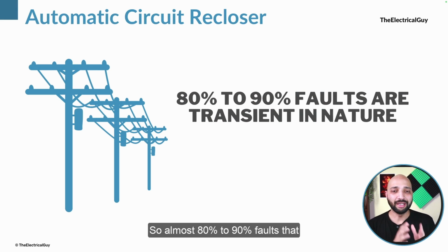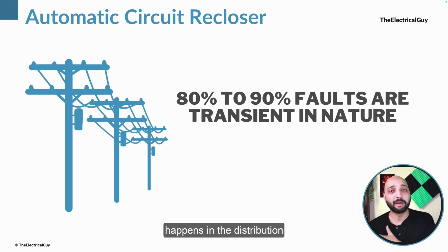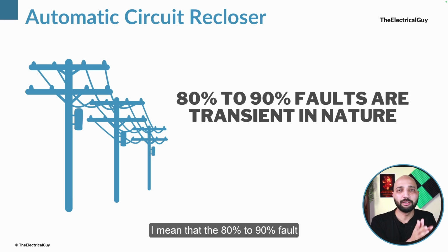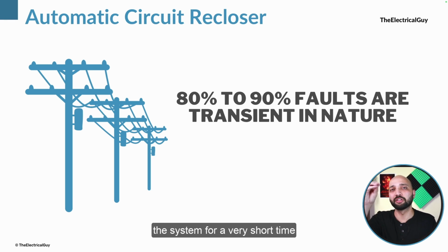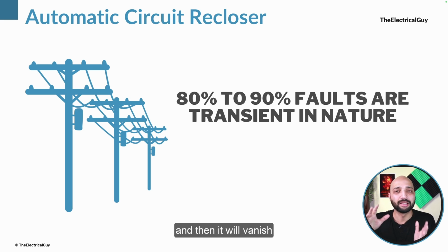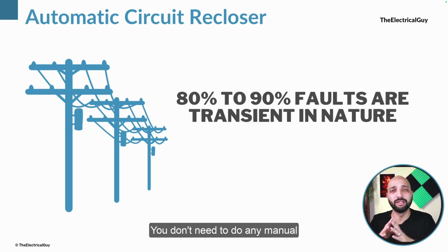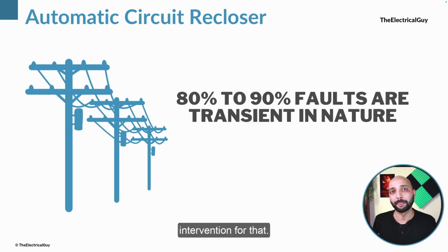Almost 80 to 90% of the faults that happen in the distribution network are transient in nature. What do I mean by that? I mean that 80 to 90% of the faults that happen in the distribution network are temporary in nature, which means they will remain in the system for a very short time and then vanish automatically. You don't need to do any manual intervention for that. It will vanish automatically. Let us understand that more with an example.